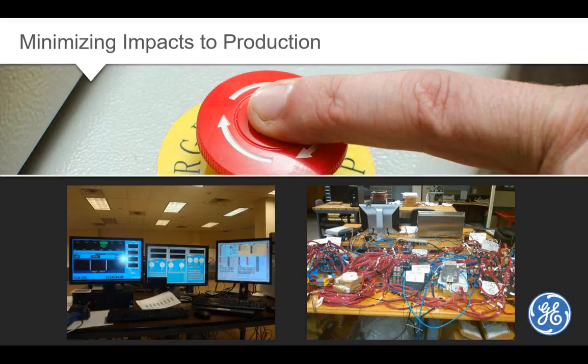Since the high voltage equipment was not available for checkout, we decided to design a simulator to act as the high voltage equipment section. Viewpoint Systems was again instrumental in developing the simulation system to properly respond to the control stimuli. You can see in the lower right the bundle of wires showing how we connected the simulation system, with the actual I/O control systems on the outside. This process greatly increased our confidence that the system would work as planned and helped minimize the startup and commissioning phase.